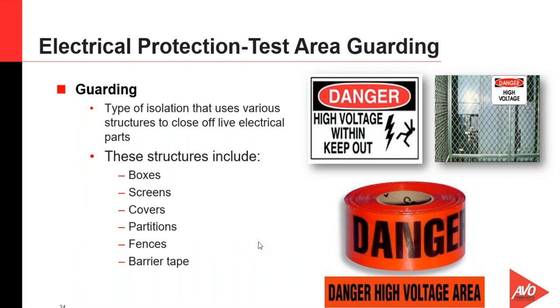Fences, substation fences have been used sometimes for the test area protection where the fence can be controlled. Partitions, covers, screens, boxes, barrier tape, all of these things are methods that can be used. Basically, we're just trying to isolate the area, give ourselves plenty of room to set up our test equipment safely, and to prohibit unauthorized personnel from actually coming in the test area.